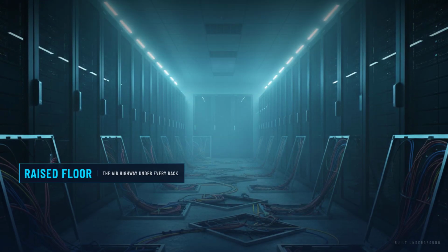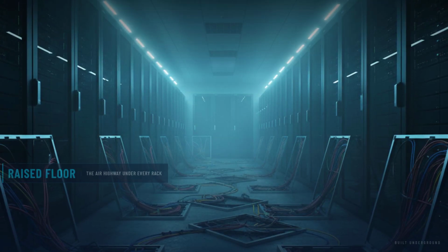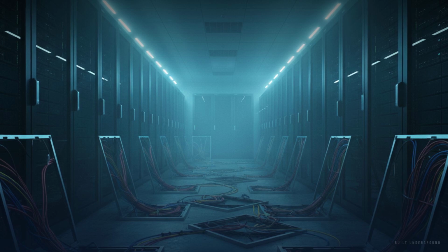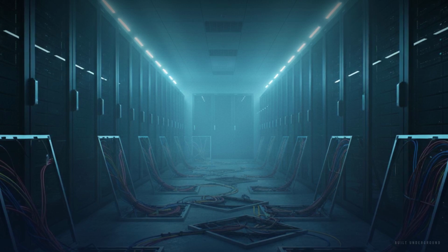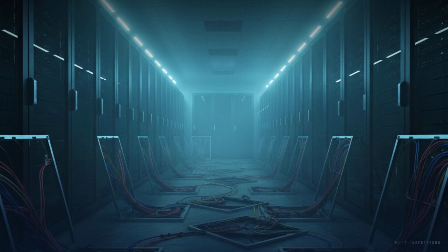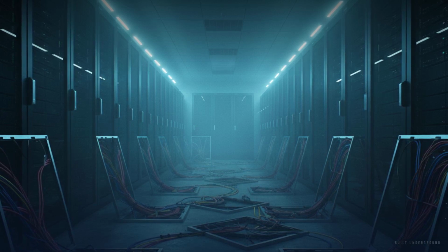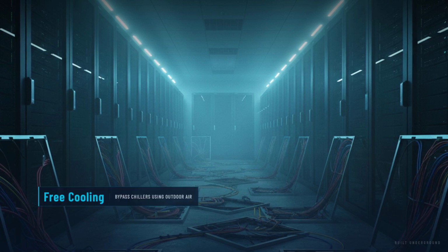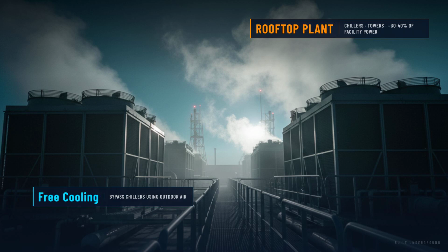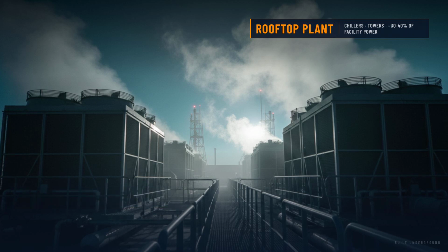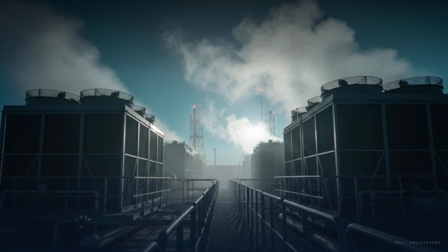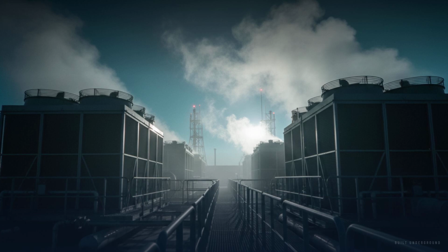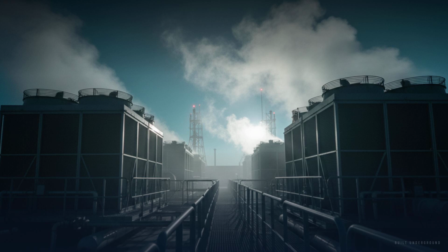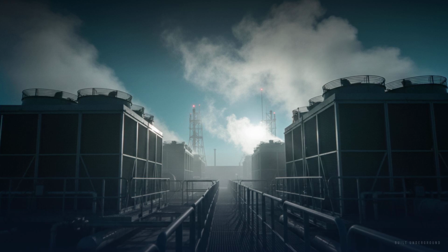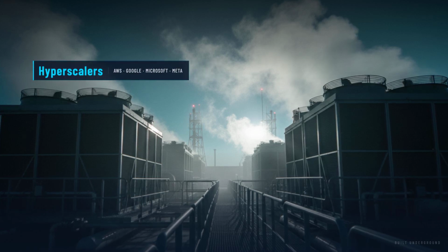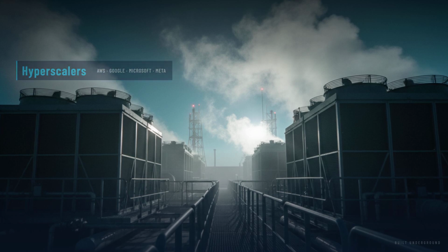The CRAHs are connected to a chilled water loop, which runs to chillers on the roof or in a plant room. The chillers reject the heat to the outside environment through cooling towers or dry coolers. In cooler climates, free cooling economizers can bypass the chillers entirely and use outside air to cool the water loop directly, which dramatically reduces energy consumption. This is one of the main reasons hyperscalers build in Scandinavia, Ireland, and the Pacific Northwest.